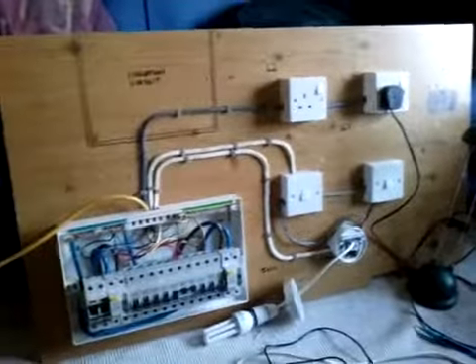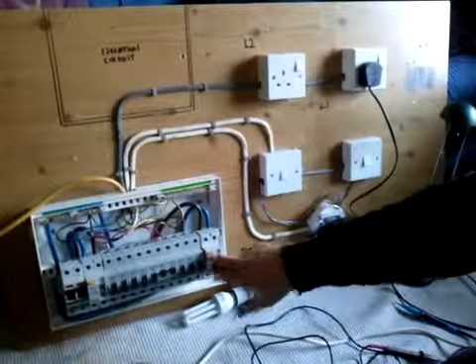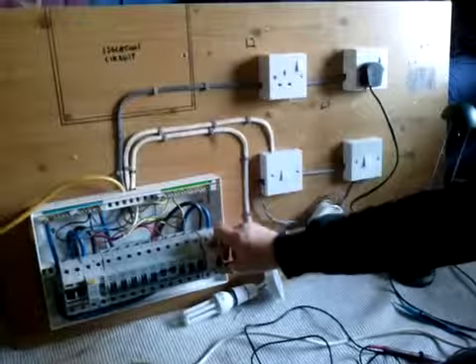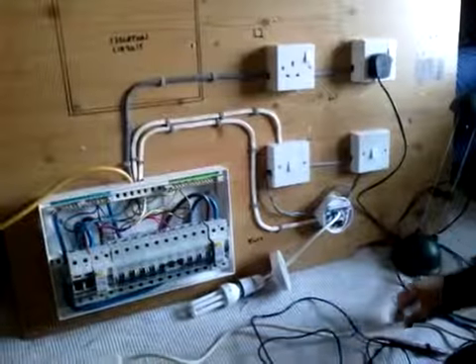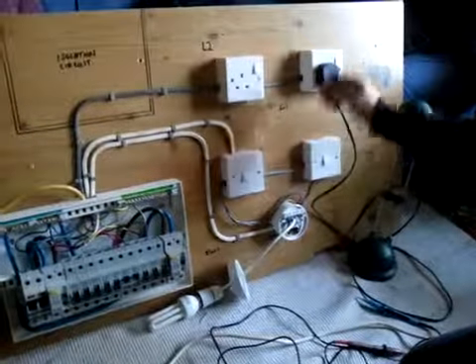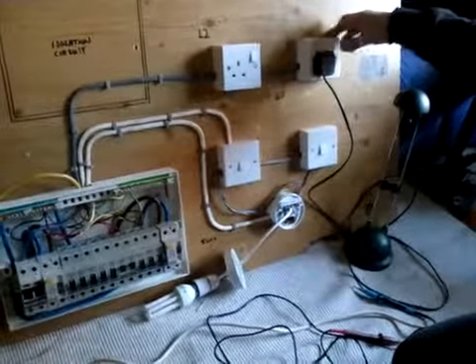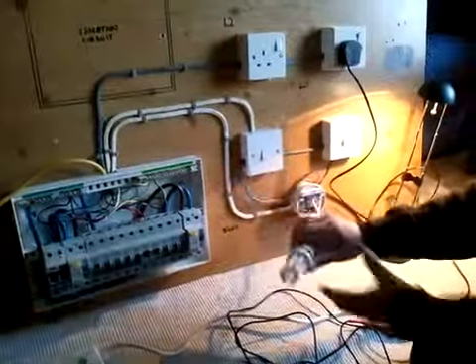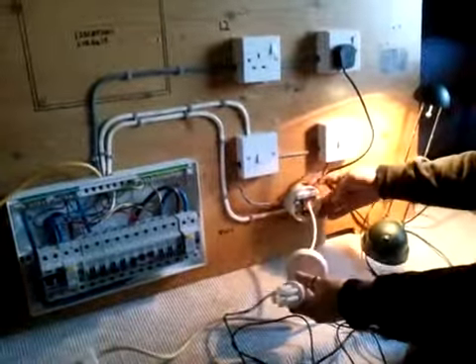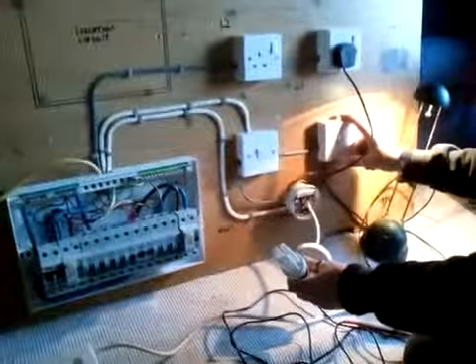Here's the rig itself. To start off with, everything is turned off. If I press these buttons, obviously it's not energised. So now, whilst I'm going to test the lamp in this row, I'll turn it on for energising here, and to make sure that I've got energy from the MCB unit, I can turn the socket on here and the light on there. That's fine. And to make sure that this lamp works, which is the circuit I'm going to be checking out, I can turn it off, on from that one, and I can turn it on from that one, on that one and off that one.